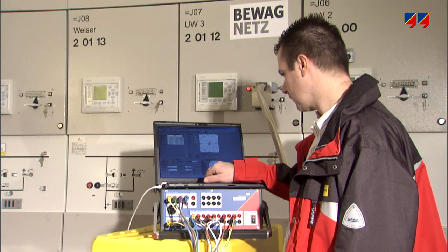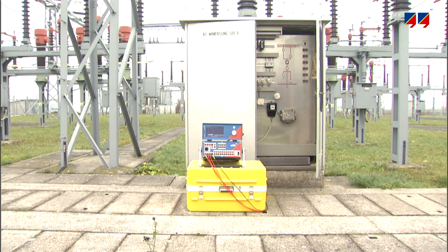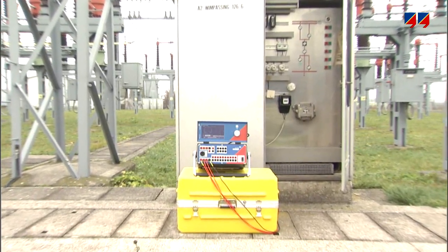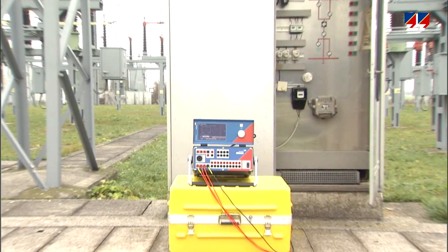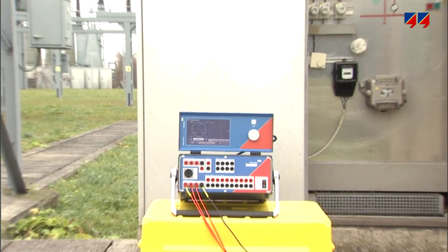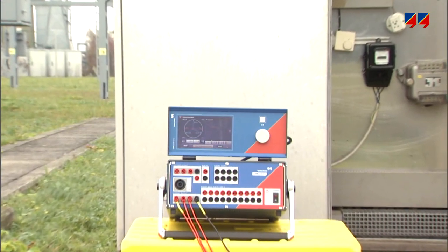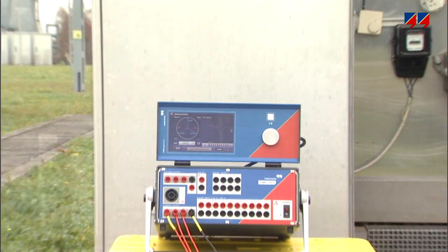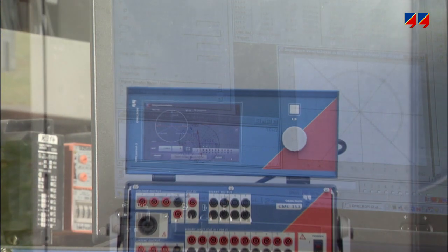Using an Ethernet interface, the CMC can either be controlled with a PC or via a removable touchscreen display, which allows the efficient manual control of standard protection tests. Because of the display's robustness and its non-reflective design, it is perfect for outdoor operation. For instance, for primary injection tests on CTs and VTs, or for checking secondary wiring. Both modes of control are independent from each other, meaning that if the PC is out of service, the CMC control provides backup operation and vice versa.